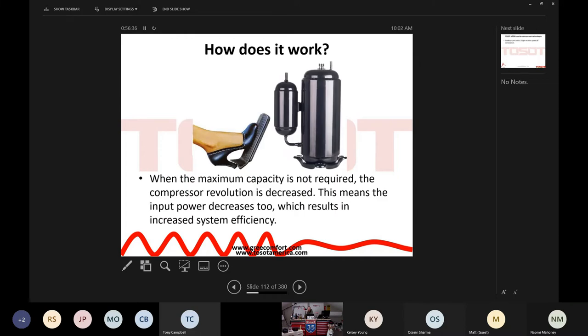When the maximum capacity is not required, the compressor revolutions are decreased. People, please. There's nothing I say today, at least about the inverter compressor, that should make your brain hurt. Don't overthink this. It truly is that simple. When the maximum capacity is not required, we slow it down, baby. Yeah, this means the input power decreases as well, which results in increased system efficiency.